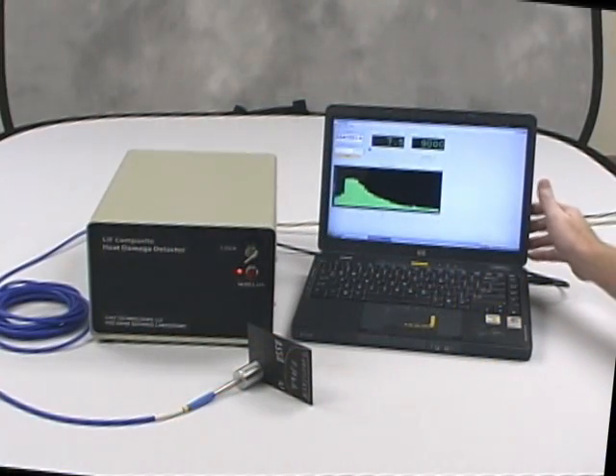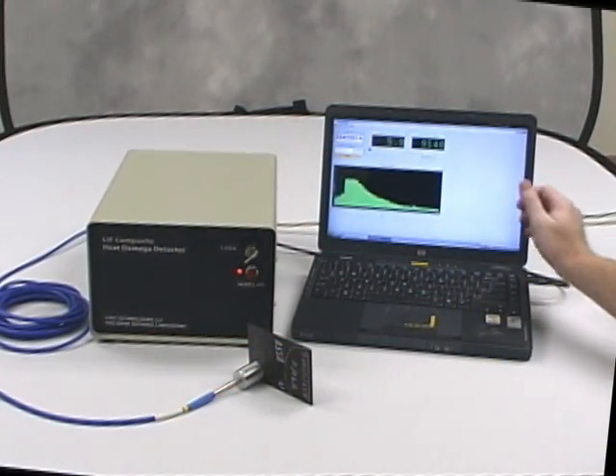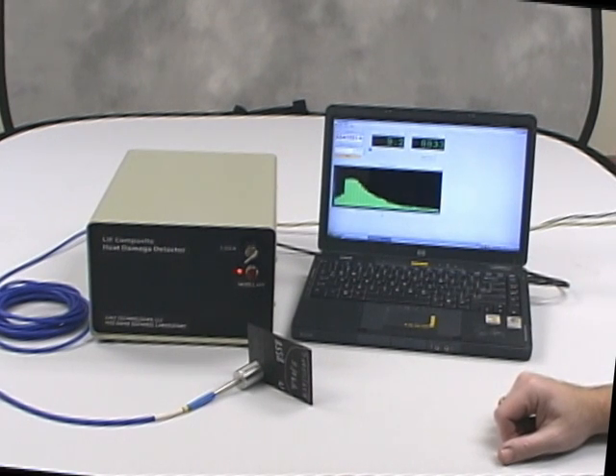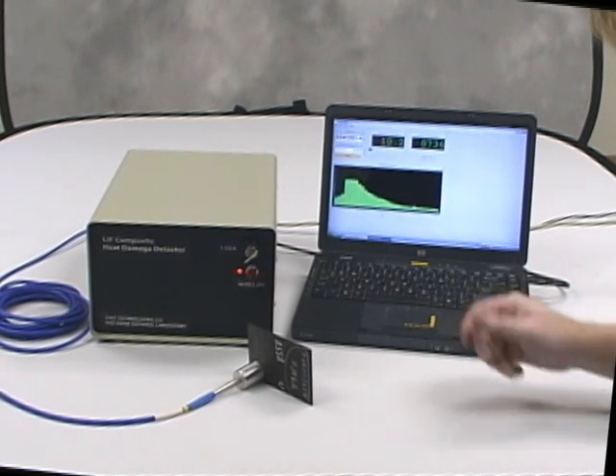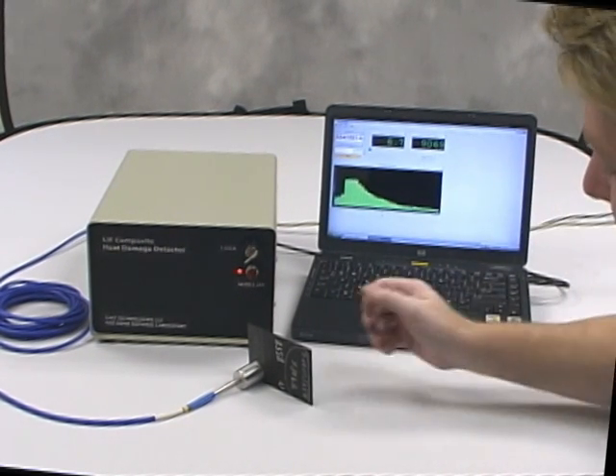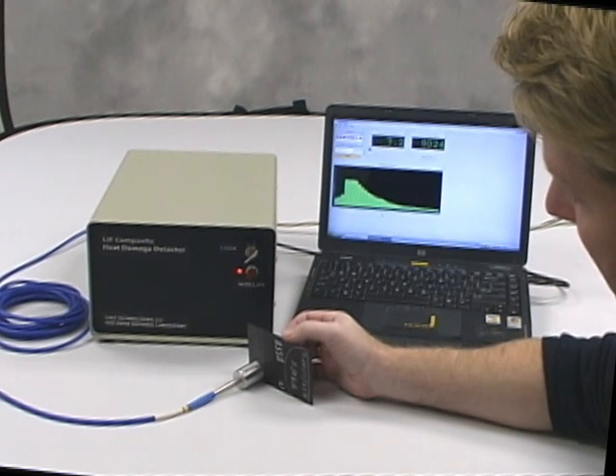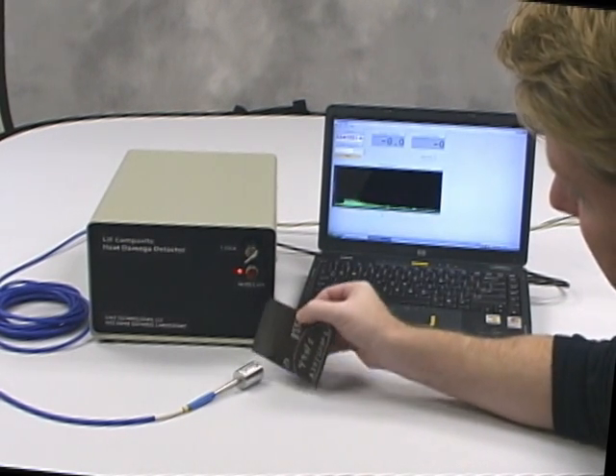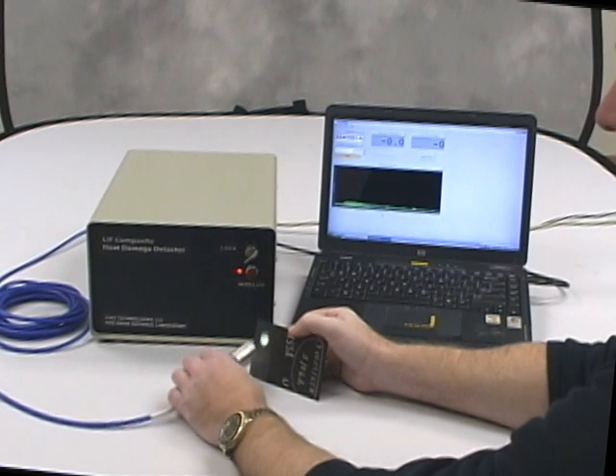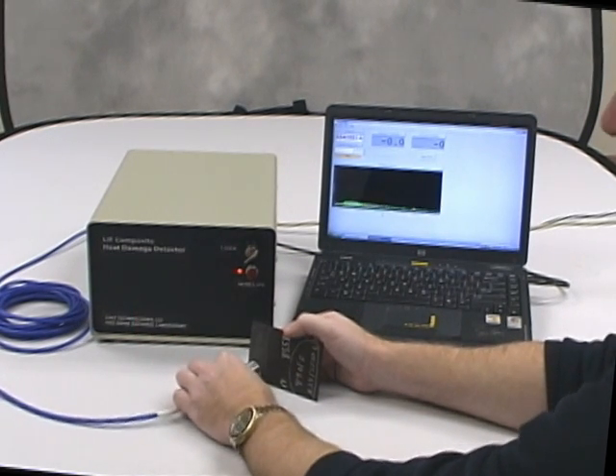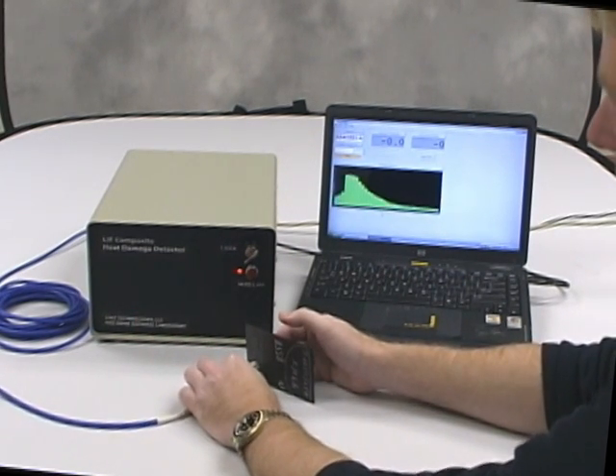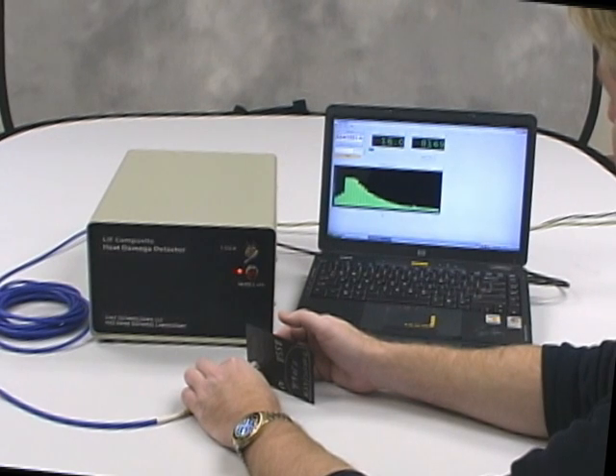The laser-induced fluorescence composite heat damage detector uses software to perform a digital demodulation of the collected and stored waveforms for each of the 32 optical channels. The laser is modulated at approximately 30 kHz. Quadrature demodulation of the LIF signal collected by the photomultiplier tube reduces interferences from ambient light by moving the signal of interest to a more quiescent region of the noise spectrum.